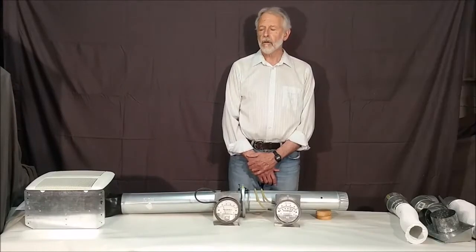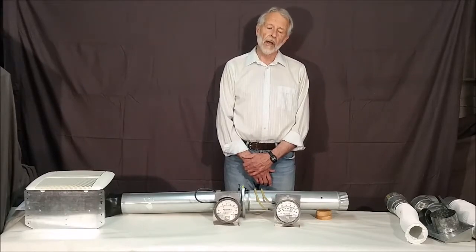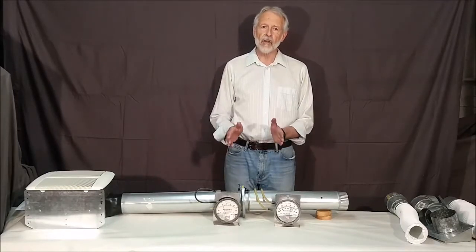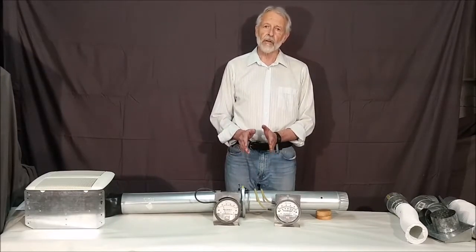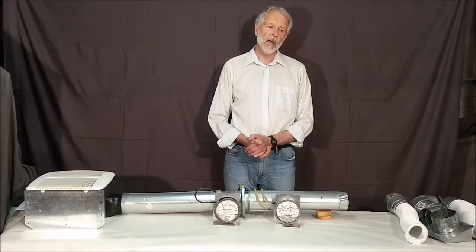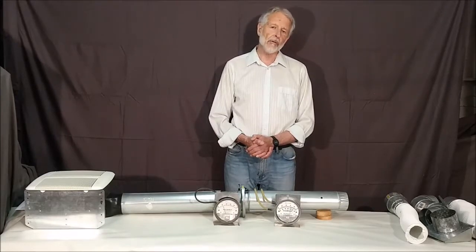The BC Building Code dictates the capacity of this fan, the principal fan, on the bedroom count, and a small factor on square footage. And that fan has to be chosen on the ability to move that much air at 0.2 of an inch of external static pressure. You also, however, must attach duct to that fan which does not exceed the 0.2, so we have tables for both smooth duct and flex to ensure that you stay within that external static pressure limitation.